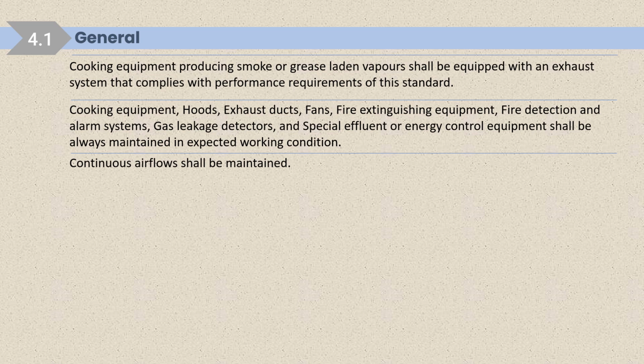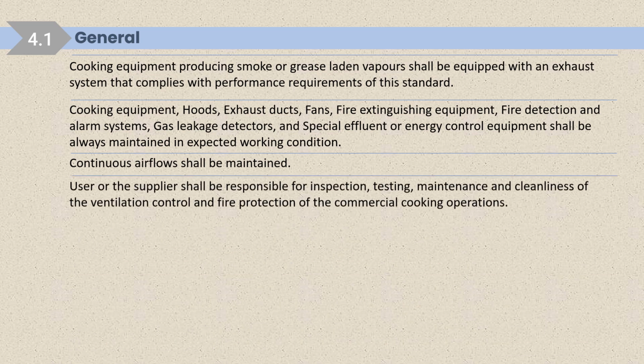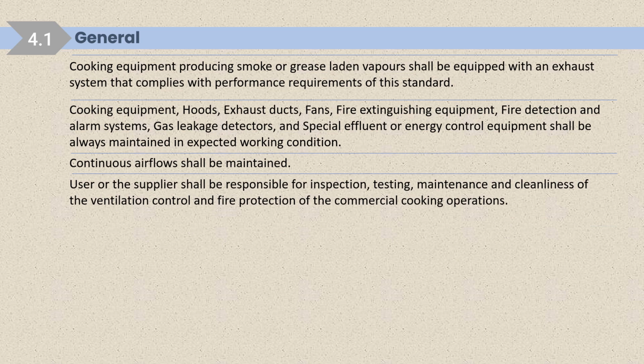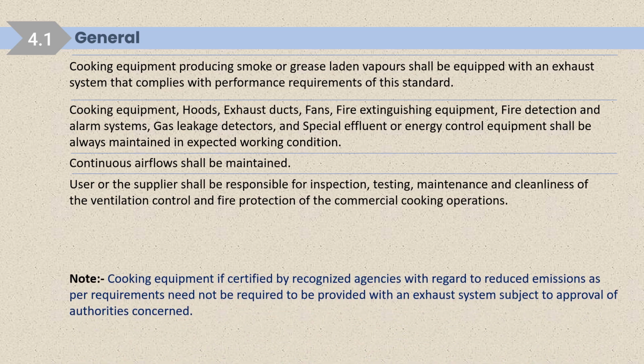Continuous airflow shall be maintained, like the exhaust hood. If we are exhausting through the exhaust hood, then we have to provide the supply air also, so that continuous airflow is maintained. The user or the supplier shall be responsible for inspection, testing, maintenance and cleanliness of the ventilation control and fire protection of the commercial cooking operation. So it is the responsibility of the user or the supplier to inspect, test and maintain, along with cleanliness of the ventilation control and fire protection of the commercial cooking operation.